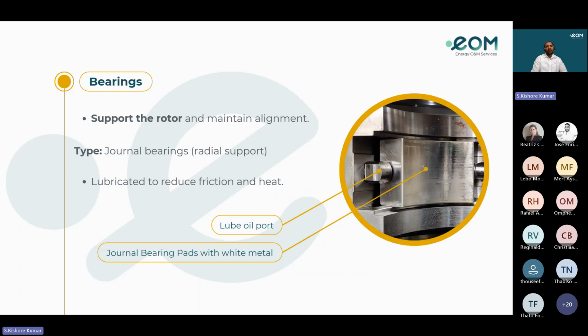And here we can see the lube oil port. The oil enters through the port or grooves and forms a wedge under the rotation. Between the shaft and the bearing, the oil wedge or film formation has to occur. Maintaining clean oil will give proper wedge formation. If any dust, foreign particles, or contamination is present, it can block the ports, and sometimes it will scratch the white metal and cause bearing damage.